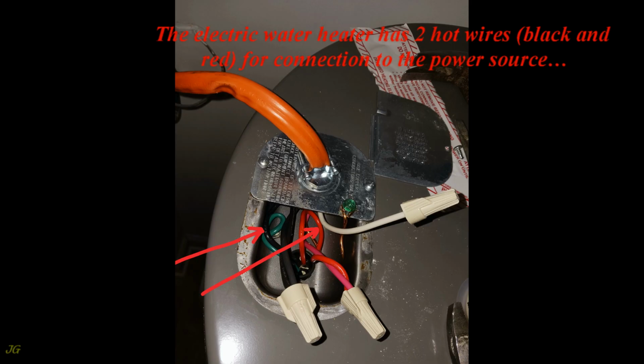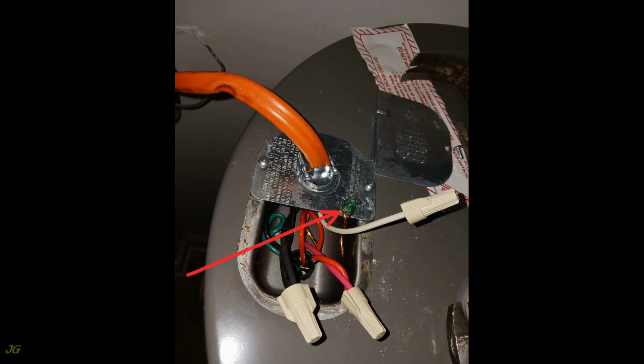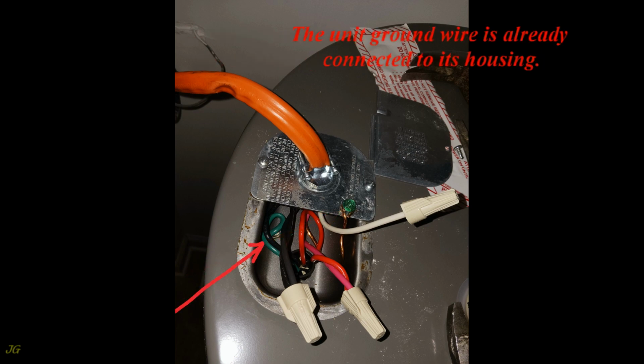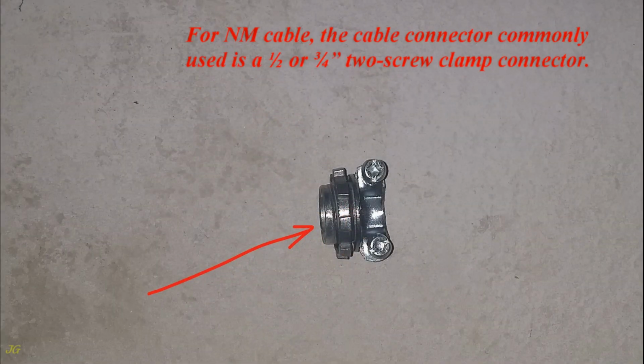The electric water heater has two hot wires, black and red, for connection to the power source, and a grounding screw for connecting the ground wire from the power source cable. The unit ground wire is already connected to its housing. For NM cable, the cable connector commonly used is a 1/2 or 3/4 inch 2-screw clamp connector.